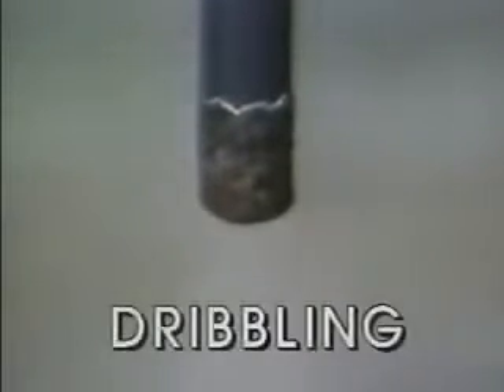Float and thermostatic traps, on the other hand, are designed to discharge condensate continuously, as long as there's a constant flow of condensate into the trap. And although an inverted bucket trap usually discharges condensate intermittently, it may have a constant small discharge if it's operating at a very low percentage of its rated capacity. This condition is sometimes called dribbling.